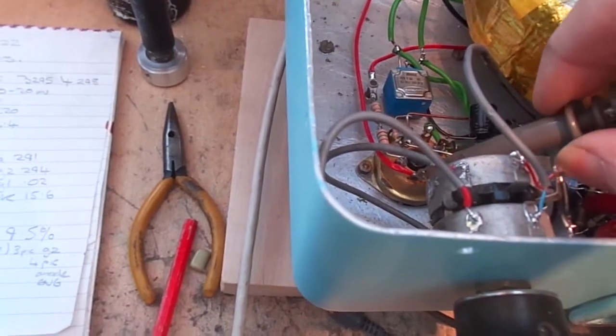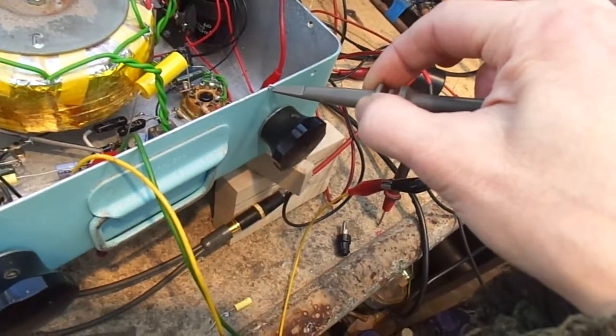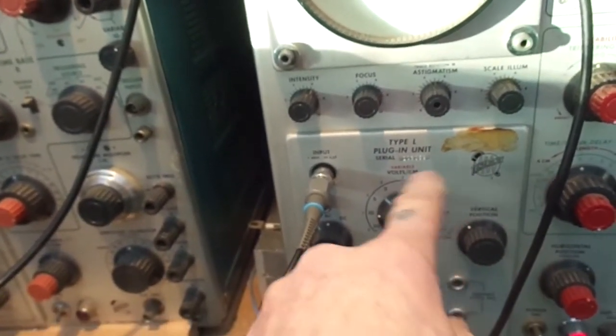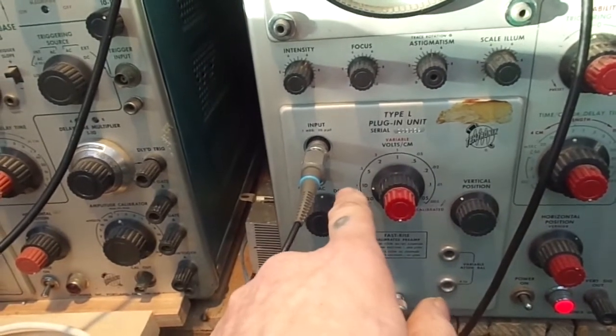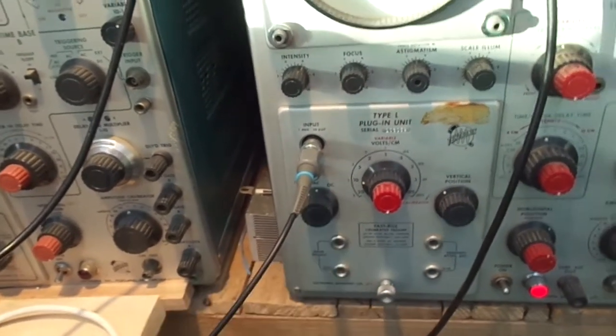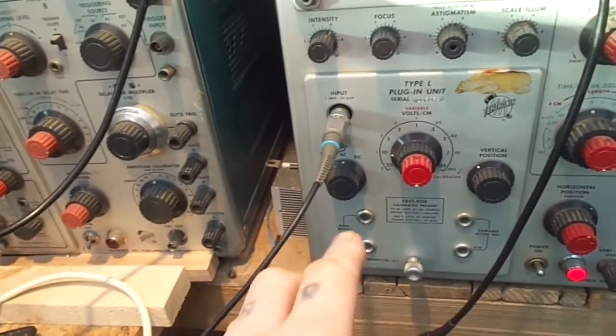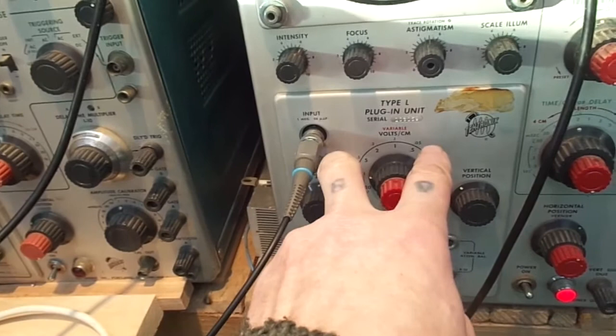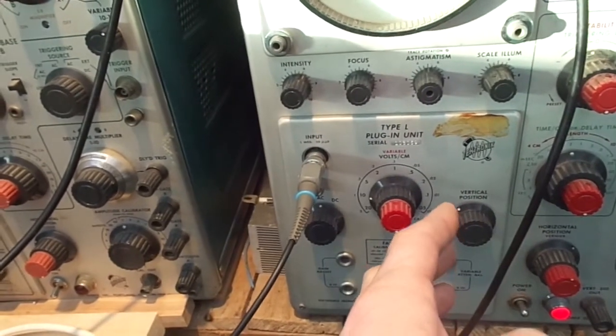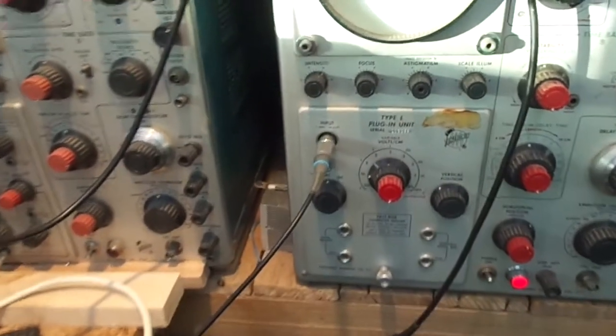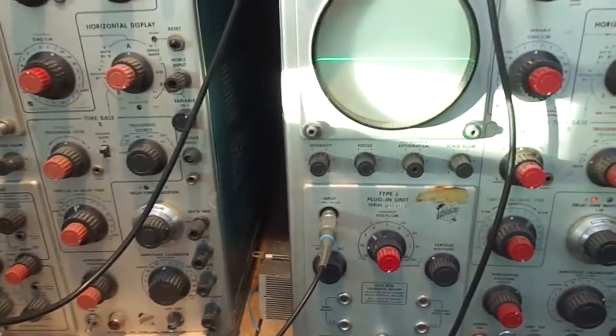Let's have a look at the screen grid. It's a good idea to discharge your probe - I'm just grounding that to chassis when taking voltage measurements, because in this vertical input plug-in there's a capacitor blocking DC that gets charged up. So basically, when you take another high voltage measurement, the capacitor is already charged, say to 200 volts, and you're sticking another 200 volts or whatever on top of that. It may exceed the maximum rating of your plug-in.